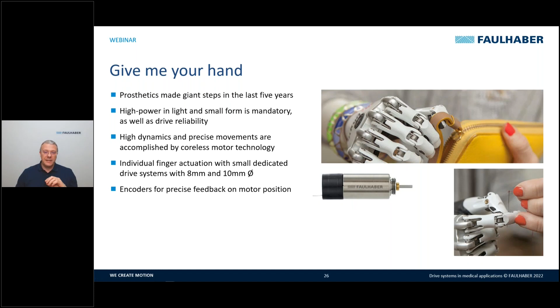Prosthetics did a quantum leap in the last 5 years. This is because it was necessary to have high power motors, light and small form factor, high reliability, high dynamics, and this was possible with the coreless motor technology. Every finger can be actuated individually with a small dedicated drive system with 8 and 10 millimeter diameter like this one. Here you can see a DC motor. We can combine it with a feedback for precise position control, and we can also use a powerful gearhead in order to have high impulsive load in this case.